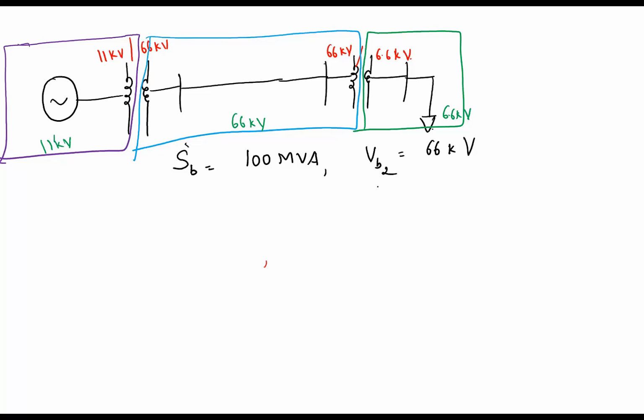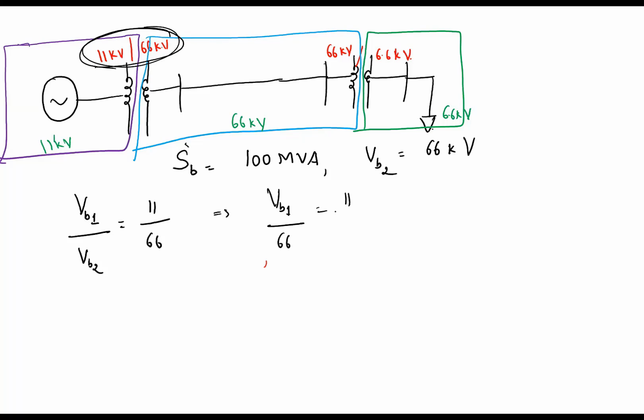Now you have to calculate the base voltage of the 11 kV section or this first section by using this transformation ratio. What is the fundamental idea with which we developed the per unit representation of transformer? The base voltages on either side of the transformer should be in the same ratio as the voltage transformation ratio. So VB1 by VB2 must be in the ratio of 11/66, because this is the voltage ratio of the transformer. So from this, already you know VB2 value, VB1 divided by 66 will become 11/66, which implies your VB1 is 11 kV.